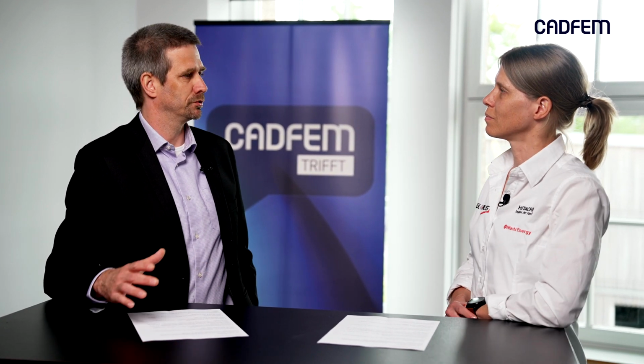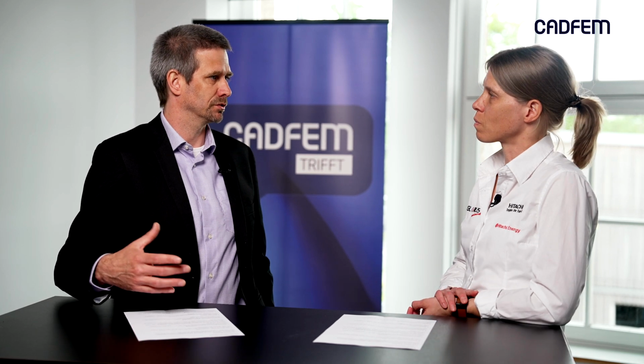So there were two points which I found very interesting. First, there is also measurement data which comes into the workflow. Is that material data, or is it really measurements on the transformer? Yeah, it depends a bit on the transformer and on the customer requirements, but there is a certain standard set of tests that have to be performed for each transformer. This includes DC loss, AC loss, short circuit impedance, resistance, and in some cases also the heat run test where the temperature rise is measured.